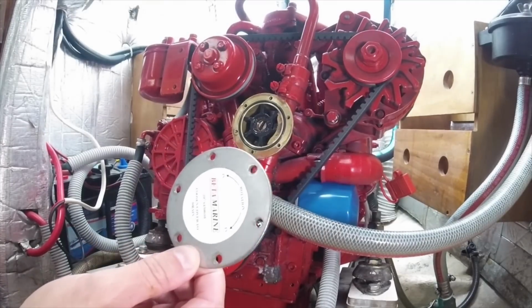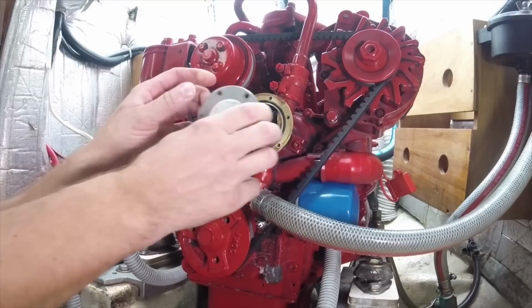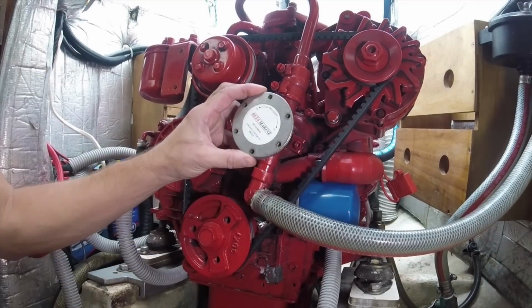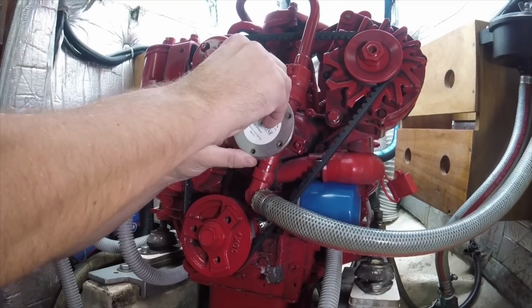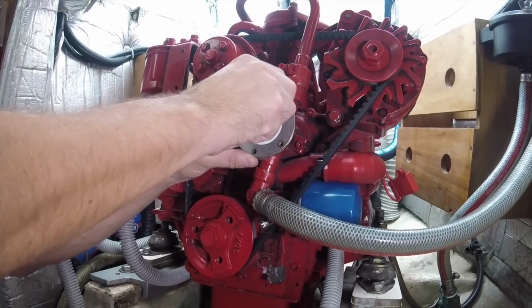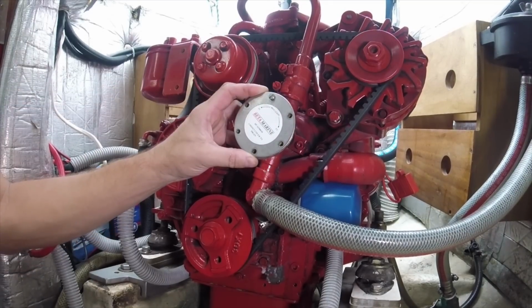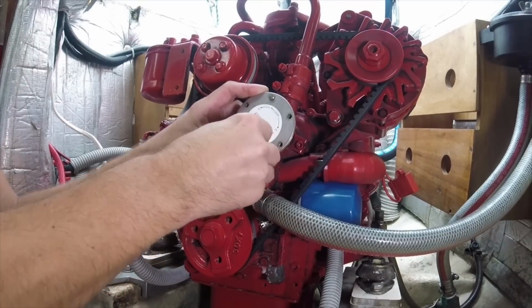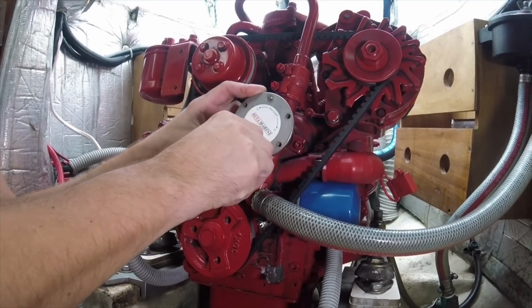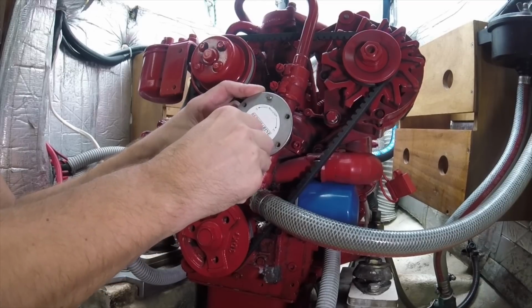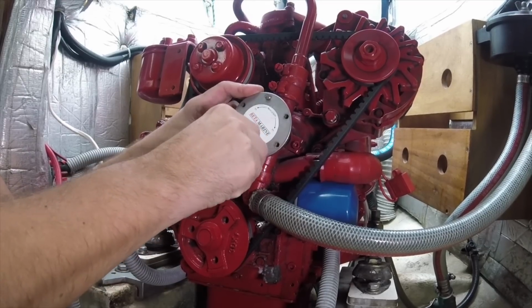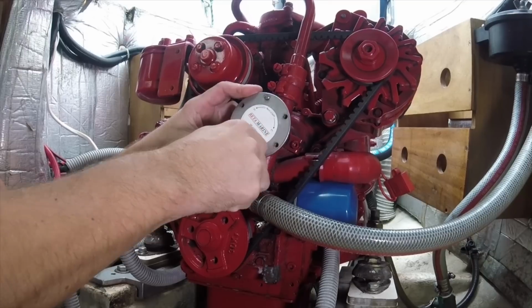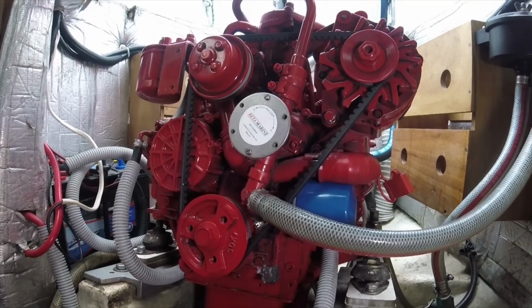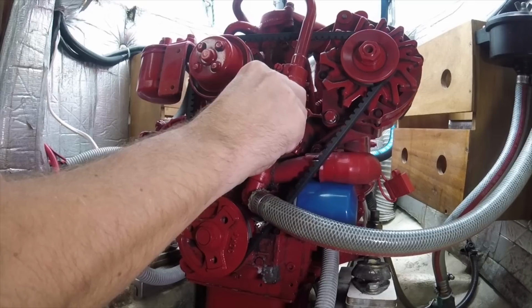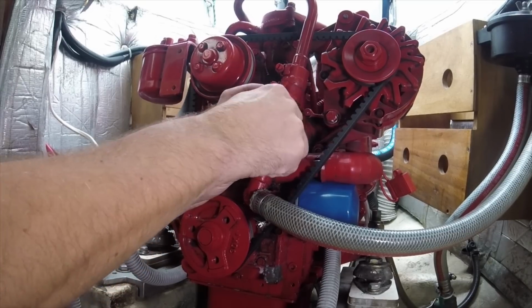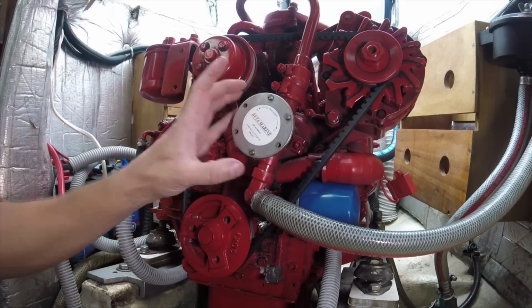Next thing to do is install the cap onto the pump. We do that by lining up the holes and finger-tightening the screws into the flange. It's important we just use our fingers, because the screws are stainless steel and very hard, while the flange is brass, and it's very easy to cross-thread these fine screws if we use force from a screwdriver.